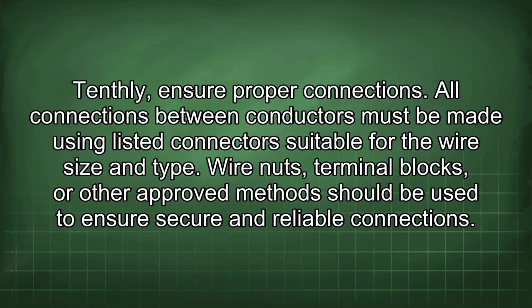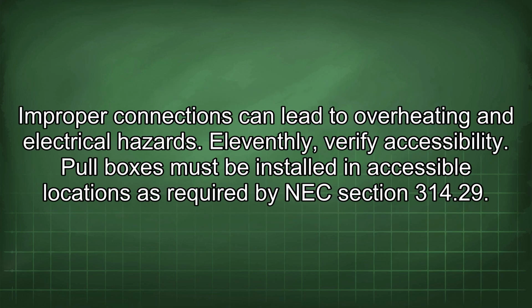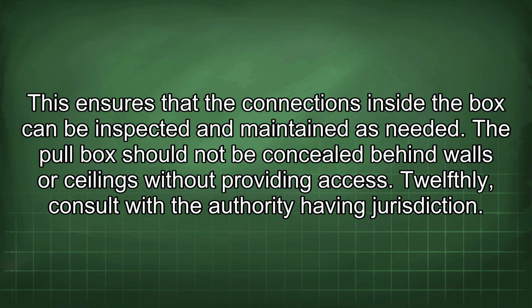Tenthly, ensure proper connections. All connections between conductors must be made using listed connectors suitable for the wire size and type. Wire nuts, terminal blocks, or other approved methods should be used to ensure secure and reliable connections. Improper connections can lead to overheating and electrical hazards. Eleventhly, verify accessibility. Pull boxes must be installed in accessible locations as required by NEC Section 314.29. This ensures that the connections inside the box can be inspected and maintained as needed.